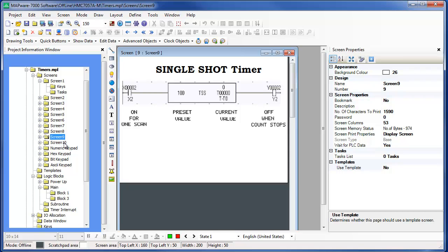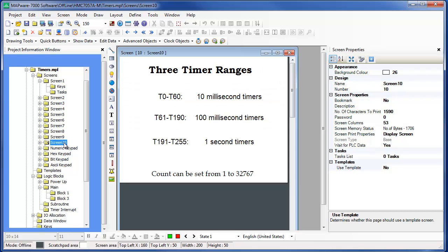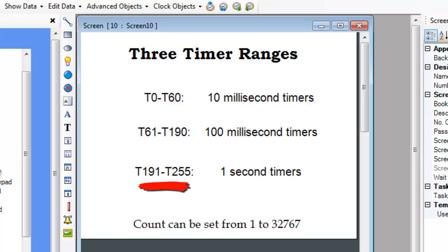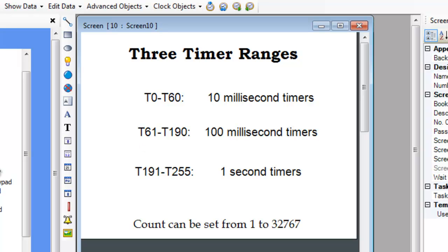You can configure any timer to increment in 10 millisecond, 100 millisecond, or 1 second intervals. This is done by selecting the timer address to fall within the address range of the interval count that you need. For precise timing down to a hundredth of a second, use address range T0 to T60. For a long count up to 3276 seconds or approximately 54 minutes, use address range T191 through T255. For something in between, use timers in the address range T61 to T190, which count in intervals of a tenth of a second. Regardless of which timer you use, the maximum value you can configure for the count is 32,767.